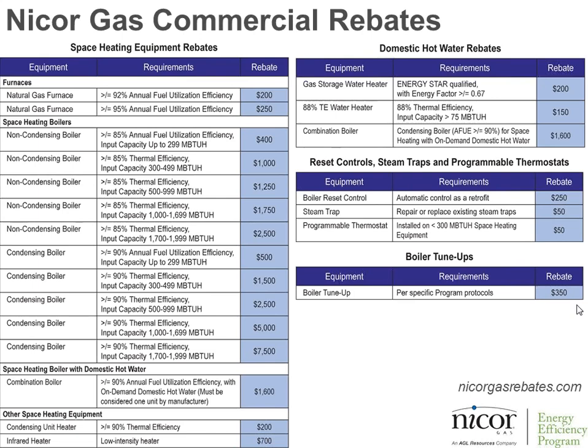Smaller rooftops or furnaces and things like that, you can add a programmable stat and get that rebate. Steam traps are a very popular rebate. You can repair or replace them for $50 per trap, and every building's got tons of traps, so that starts adding up pretty quickly. And you can also add outside air reset controls to an existing boiler plant for a $250 rebate. There's a few other things on the screen here as well, as you can see.